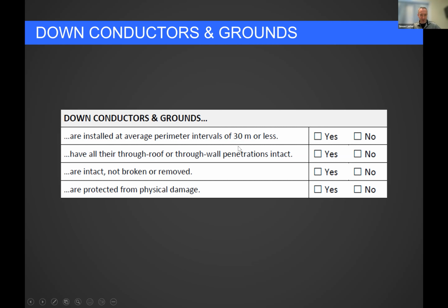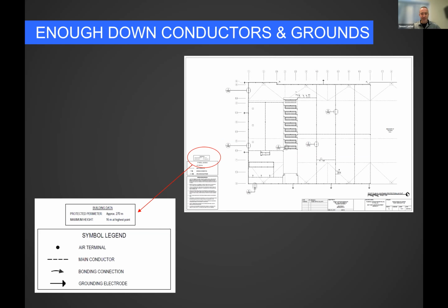So we'll go through and check whether a building has enough down conductors and grounds. Here's an example of a submittal document I put together for a data center project in Calgary. I always do this on my drawings, though you wouldn't normally see my submittal drawings - that's for the engineer. I called out the building's protected perimeter as approximately 270 meters, so if we need a down conductor every 30 meters maximum, I'm going to need 9 on this building.